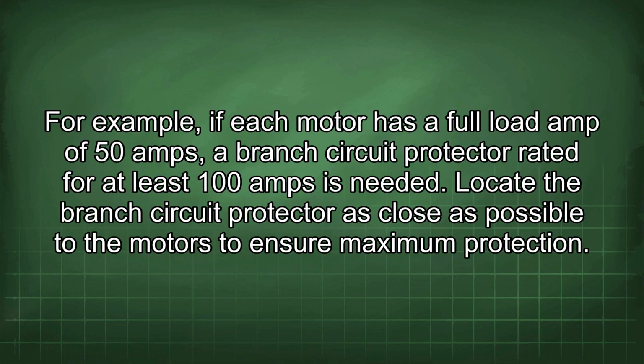For example, if each motor has a full load amp of 50 amps, a branch circuit protector rated for at least 100 amps is needed. Locate the branch circuit protector as close as possible to the motors to ensure maximum protection.